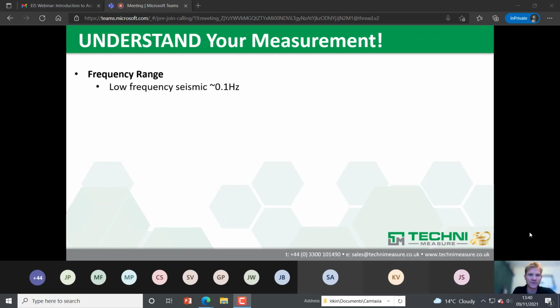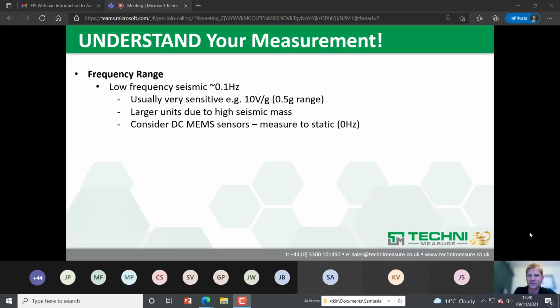As Keith mentioned, in the low frequency seismic range, typically with a piezoelectric accelerometer, you can get down to 0.1 hertz or just below. They tend to be very sensitive accelerometers, like 10 volts per G, for example, with a half G range. They're very large because they have a very high seismic mass in them. You might want to consider DC MEMS sensors, or variable capacitance sensors, which measure down to static G or 0 hertz if you're looking at a low frequency measurement.